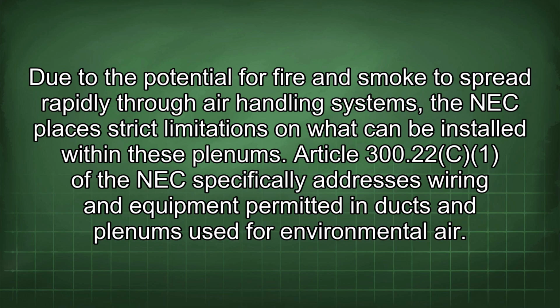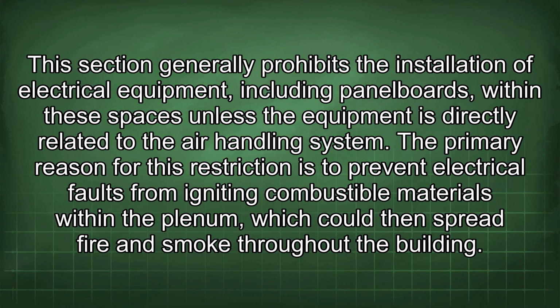Article 300.22 of the NEC specifically addresses wiring and equipment permitted in ducts and plenums used for environmental air. This section generally prohibits the installation of electrical equipment, including panelboards, within these spaces unless the equipment is directly related to the air handling system. The primary reason for this restriction is to prevent electrical faults from igniting combustible materials within the plenum, which could then spread fire and smoke throughout the building.